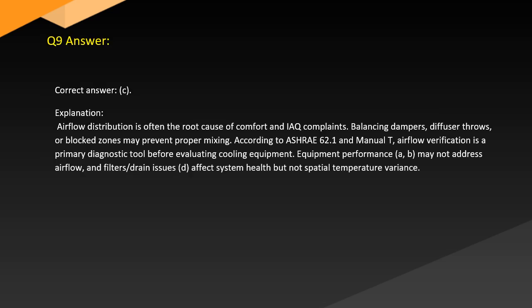Answer. Correct answer: C. Explanation: Airflow distribution is often the root cause of comfort and IAQ complaints. Balancing dampers, diffuser throws, or blocked zones may prevent proper mixing. According to ASHRAE 62.1 and Manual T, airflow verification is a primary diagnostic tool before evaluating cooling equipment. Equipment performance, A and B, may not address airflow and filters/drain issues. D affects system health but not spatial temperature variance.